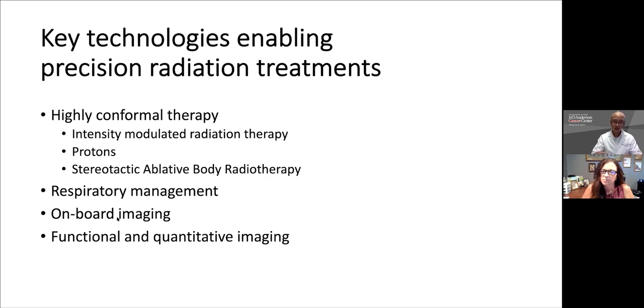we have to be assured that the patient's in the same position on a day-to-day basis. And so this is what the onboard imaging helps us to achieve. We have an image guidance system that's integrated with our linear accelerators that deliver the radiation, so that we can be assured that the patient's in the same position and that the tumor is in the right location in the path of those radiation beams so that we hit the right target.